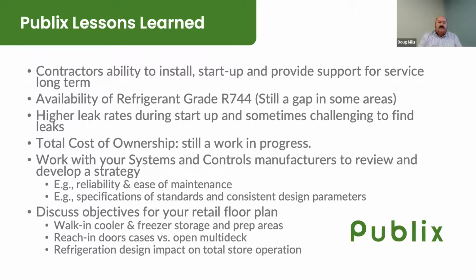It's sometimes challenging. The other thing with leak checking these systems early on - we've been doing this since 2010 - the leak detection systems, there were only a couple of units designed for detecting CO2. So our first round of leak checking was 3 or 4 people with bottles of soap solution, spraying down every fitting and valve on the rack, which was pretty ugly, I'll be honest. But since then, companies have developed leak detection sensors for CO2, so that's pretty much a non-issue at this point.